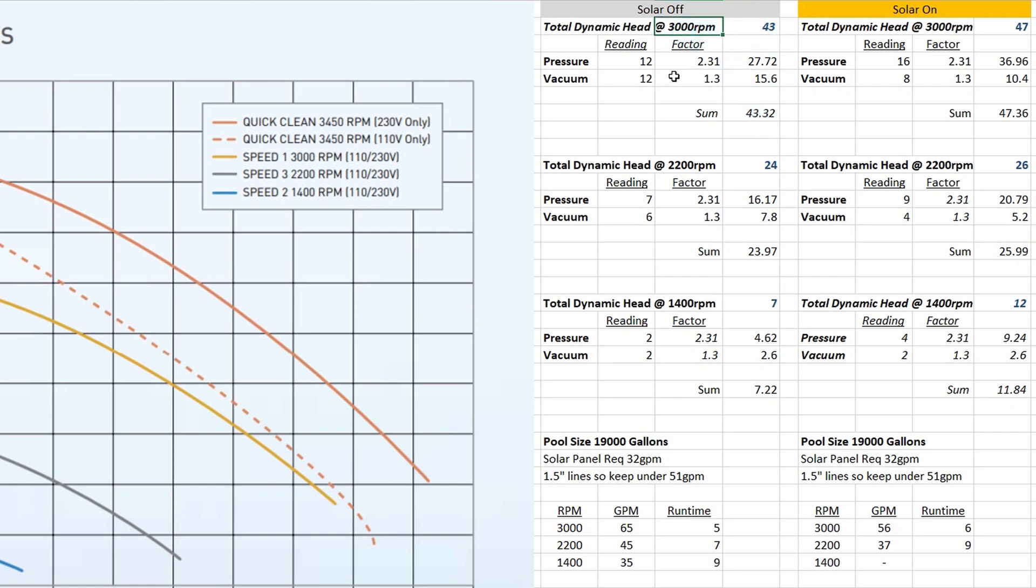So for example at 3000 RPM I had a pressure reading and vacuum reading both of 12 and you just multiply the pressure reading times 2.31 and the vacuum reading by 1.3 and that gives me 27.72 and 15.6 which when added together comes out to 43.32 so we'll round that to about 43.